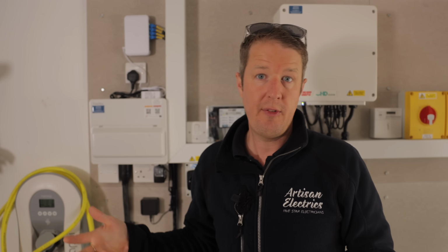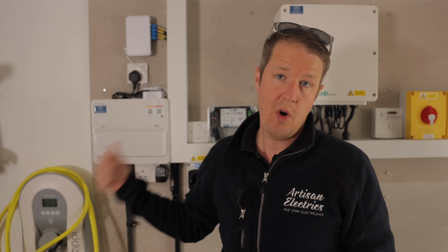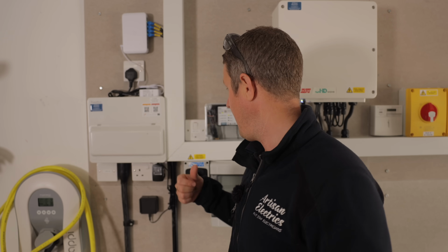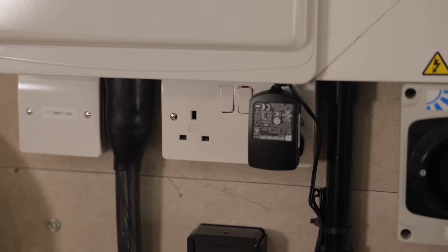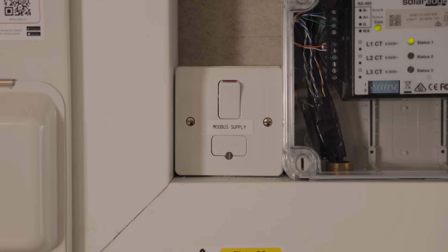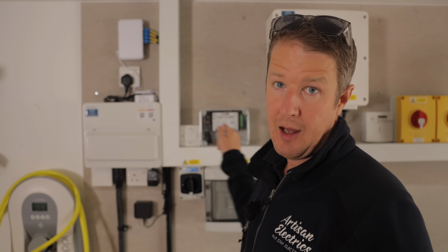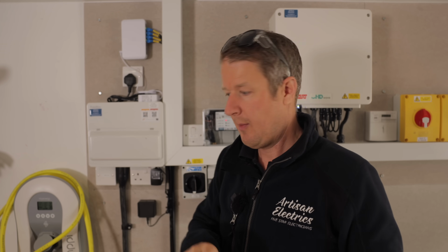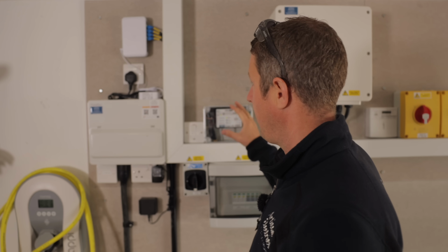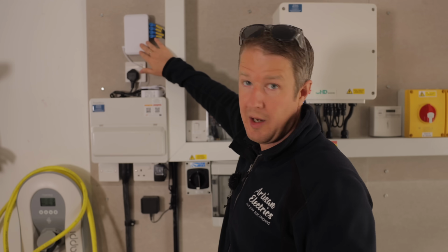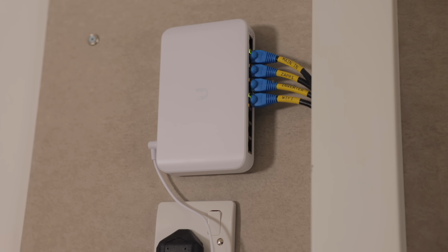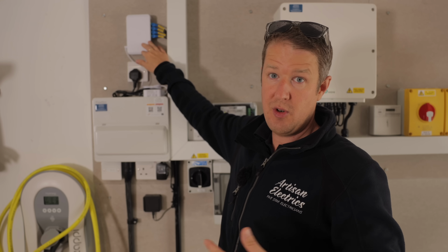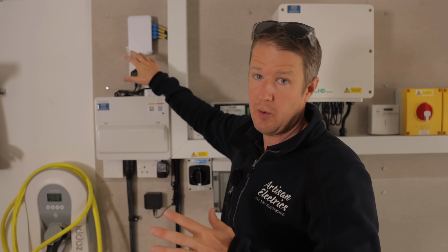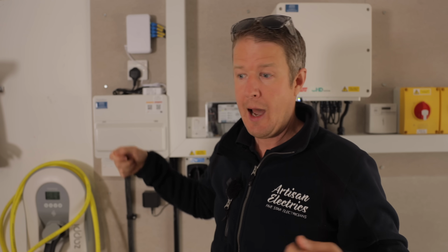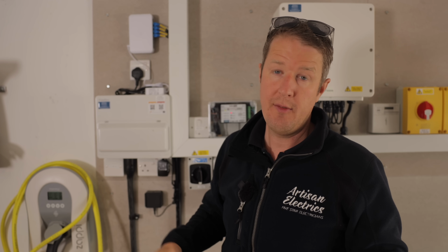So you can either run it off an existing socket circuit or just run in a separate radial, which is what we have done. We run in a separate radial for this socket here and the supply for the SolarEdge Modbus anyway. So we're going to just loop out of that and install an additional fused connection unit for the Libbi controller. The other things that we've got here are, we've got a hardwired Ethernet. Because we're remote from the house, we ran a data cable from the router in the house to here. We've got hardwired Ethernet, so we're going to hardwire everything. However, you can connect the Libbi controller via Wi-Fi, and it will work as long as you've got good Wi-Fi signal.